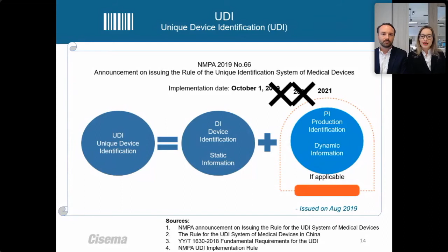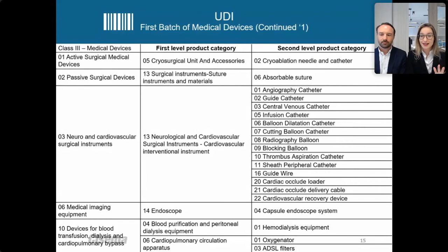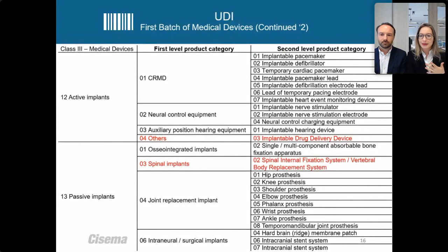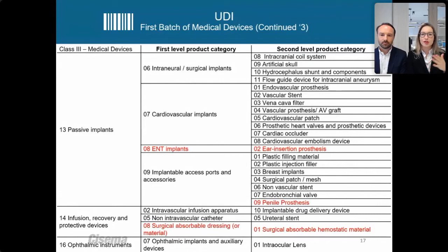Now, Hamish already mentioned that the medical devices that are affected by UDI are released in batches, and of course, if you are in the first batch, I would assume you probably already know this because the implementation date is 1st of January. Nevertheless, I want to include it here, especially because there has been a revision. So in the following 3 slides, you can see the first batch of medical devices. For instance, all of them are risk class 3, very high risk class. A lot of them are implanted devices, such as guide wires, or here you can see implantable drug delivery devices. What I highlighted in red are the revised editions, also ear insertion prostheses. So this is the updated batch, and the NMPA will release more and more batches until eventually all medical devices in China have UDI.